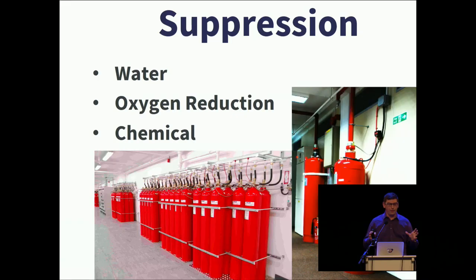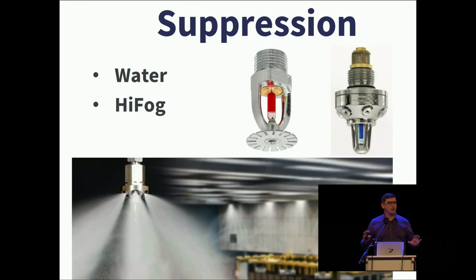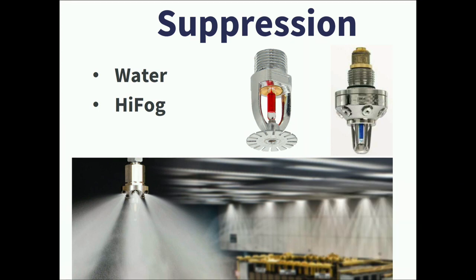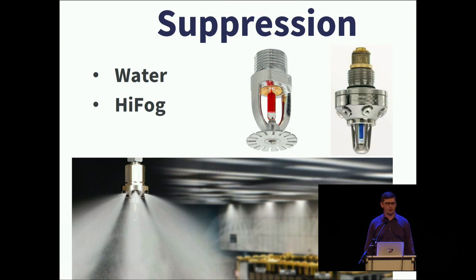So, quickly on the fire suppression side. You've got three main types. Obviously, we all know about water. It's the most common. In data centers, we obviously don't really like water all that much. We've got the option of reducing the oxygen down, and we've got interrupting that chemical reaction. I've never deployed a water fire suppression system in a data center. I've seen it done in a few places. As I understand it from speaking to people that have done that, they're more interested in protecting the building rather than the IT equipment. And that's a sensible and reasonable approach.